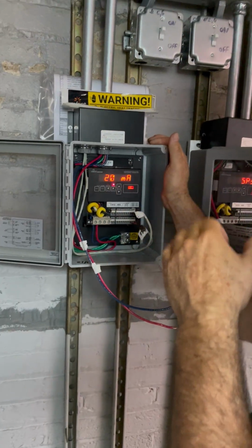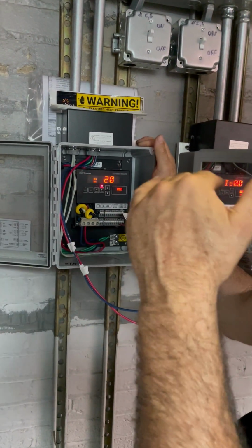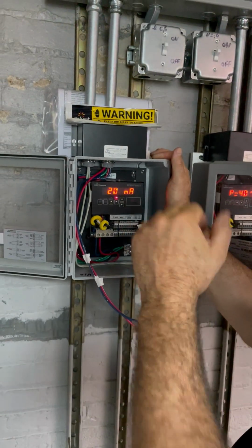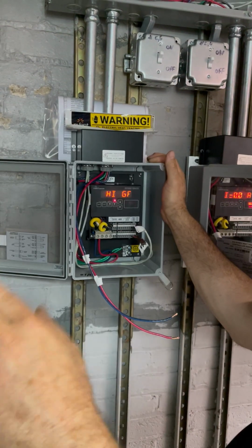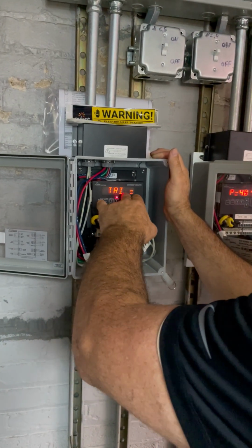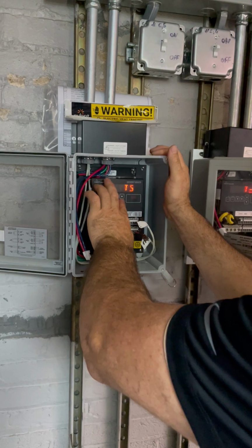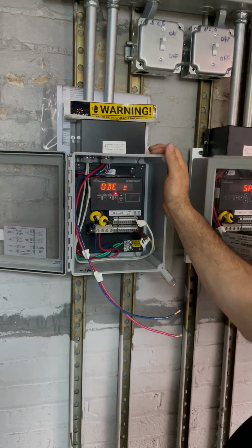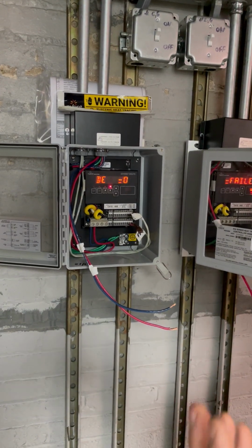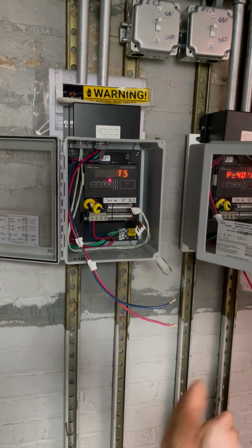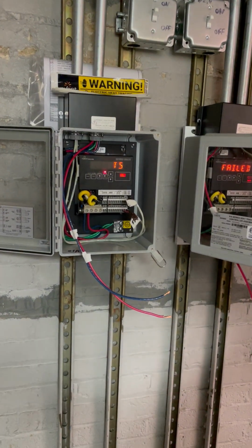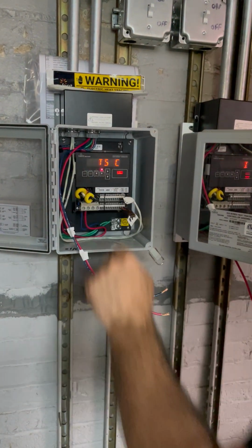This provides ground fault protection at 30 milliamps. It will trip. It also has a warning for you at 20. If something's degrading, then it'll alarm at 20. It will trip at 30. TS fail mode. If you lose a sensor, do you want it to go on or do you want it to go off? Safety shower, you'd probably want it to go off. Here, we want it to go on. We don't want anything to freeze. So we're going to leave that as on.